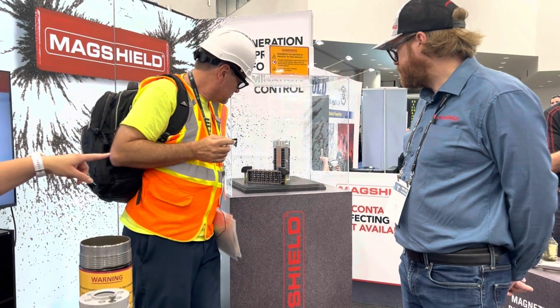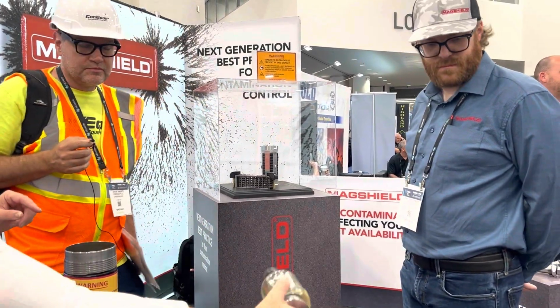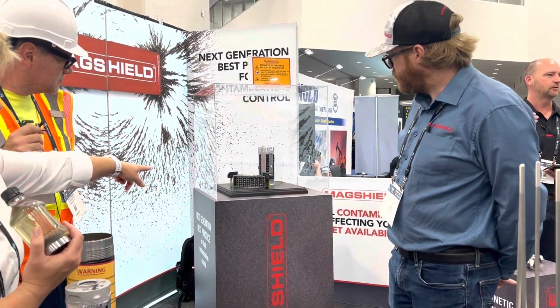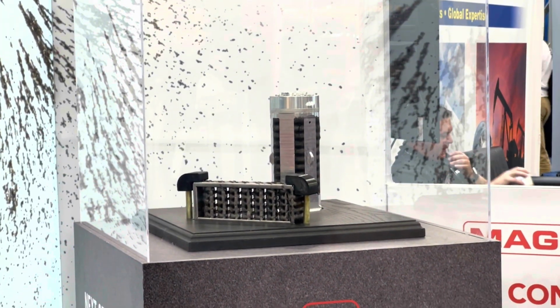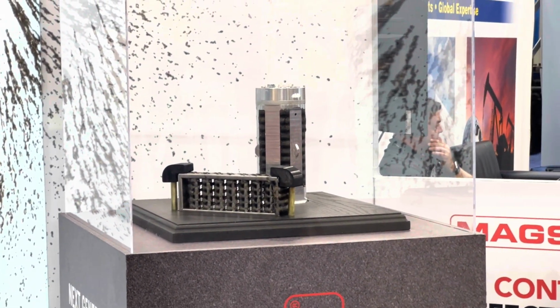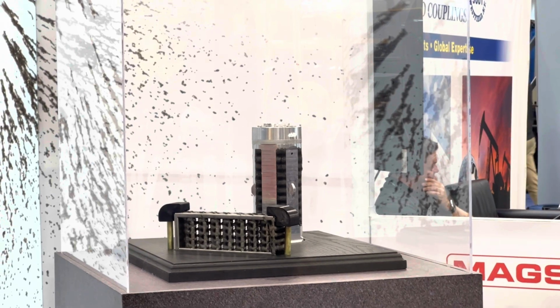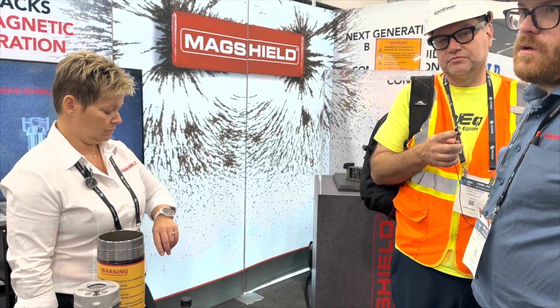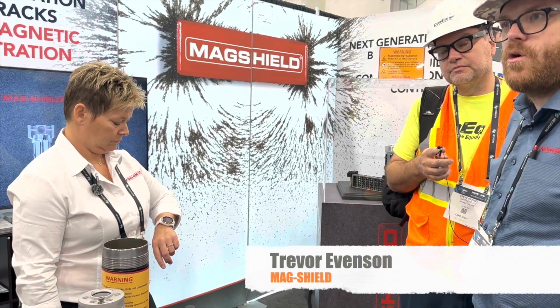This shows the MagShield, the little rectangular one on the front. That is post-failure, showing how much contamination that one collected before the machine shut down. Not very often — if you have a failure to that level, of course you'd have to clean it then.